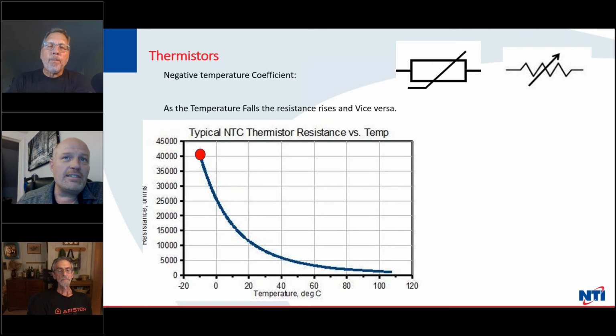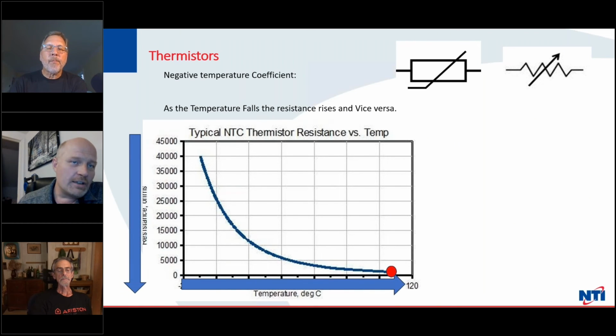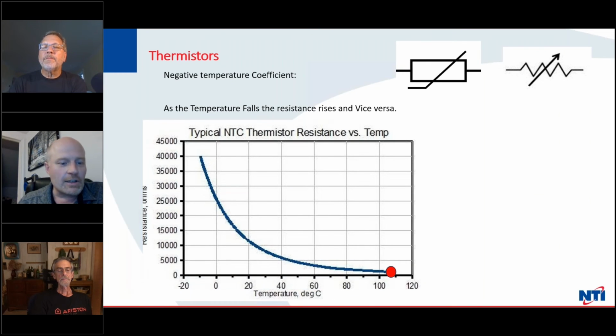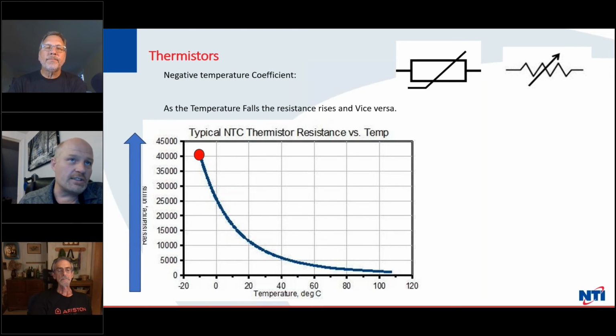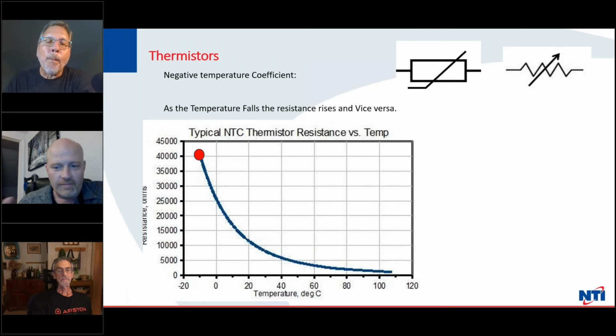So there's a resistance chart for a typical 10K thermistor. They call it negative temperature coefficient because as our temperature rises along the bottom, the resistance falls. So the two are doing opposite things to each other. And as our temperature falls or gets colder, the resistance goes up. And it's going to create a curve, something like what you see there. Don't worry about this. If you Google 10K thermistor, you can get this resistance chart basically anywhere on Google. It's also in every manual, and you can use this as a comparison to test your thermistors and see if the reading you get on the screen seems valid. The other thing you can do is use your hands.